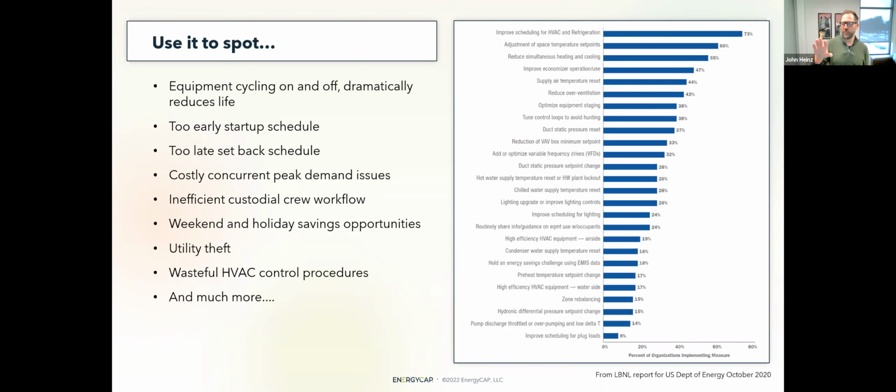just alone, you can see a number of them are just scheduling. So this isn't even going out and purchasing new equipment. And some of these are purchasing equipment. Just changing scheduling has a big return on investment. And that's something you can pretty much do today, but you need the ability to monitor it. You need to monitor what the schedule is today, what a heat map is, where your largest volume of consumption is. Are your systems actively turning off and setting back deep enough during off-peak times, and so on and so forth.